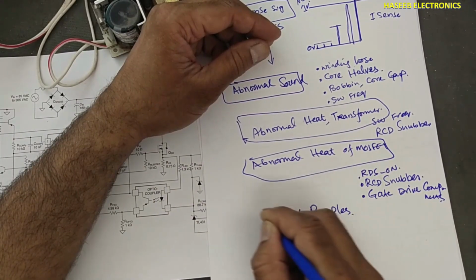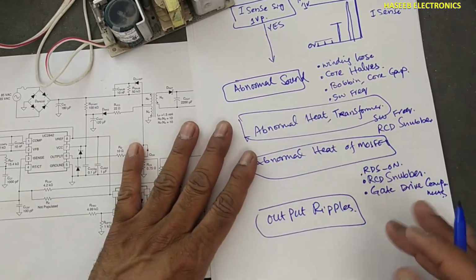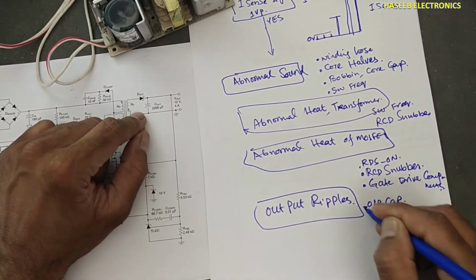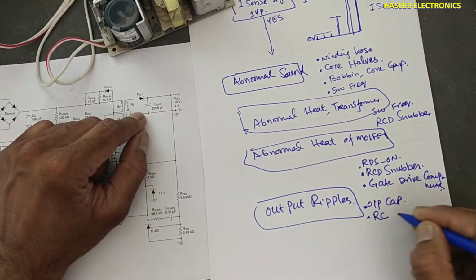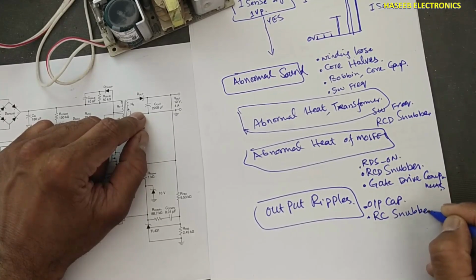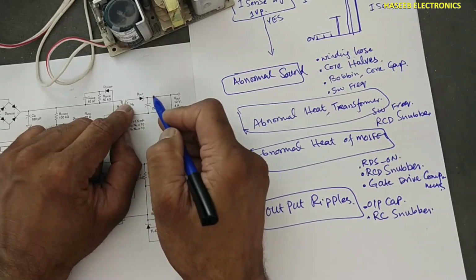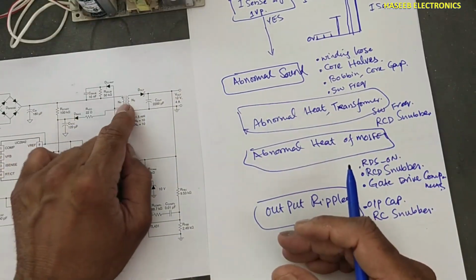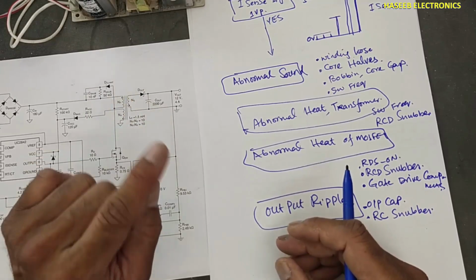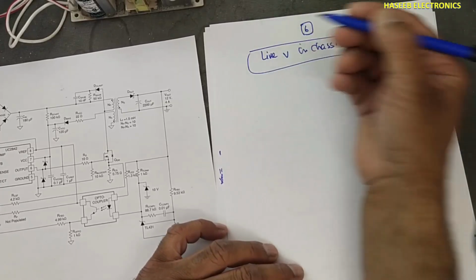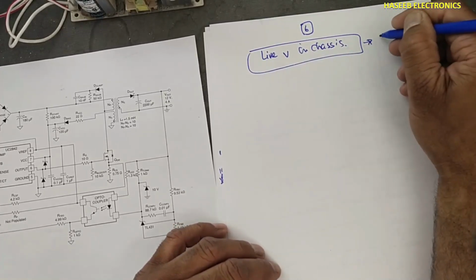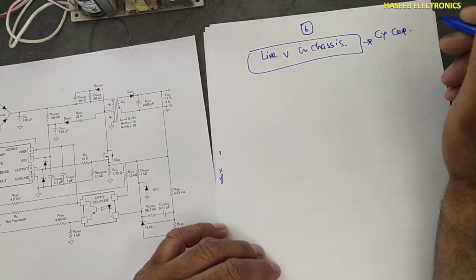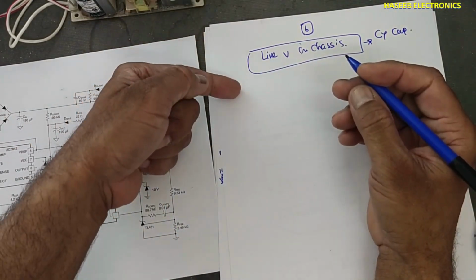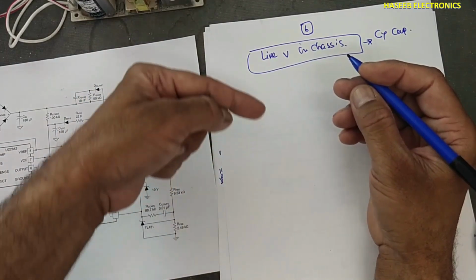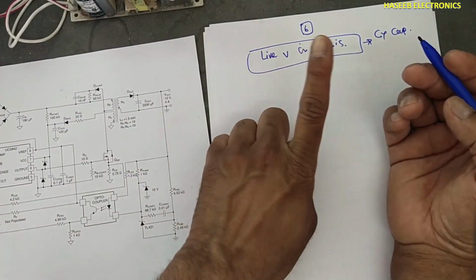Then output ripples. If there are more ripples in the output, it might be that this capacitor is bad. Sometimes there is an RC snubber for the rectifier, that is bad, that is connected across this Schottky rectifier for fast recovery. For high frequency switching applications, that RC snubber is bad, this RCD snubber. If you find live voltage in the chassis, most of the time a class Y capacitor is damaged, that is connected between line and chassis, neutral and chassis, that causes live voltage in the chassis.